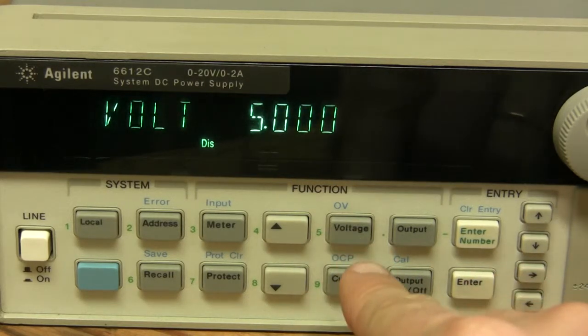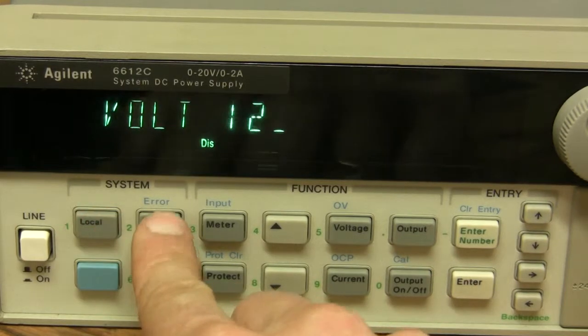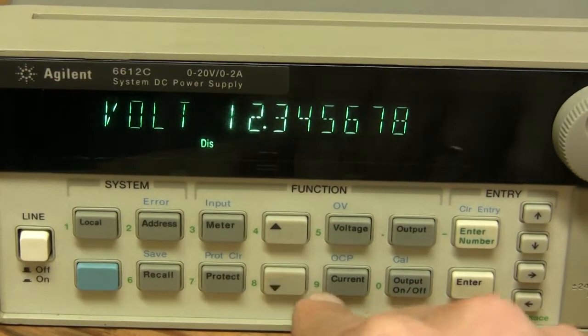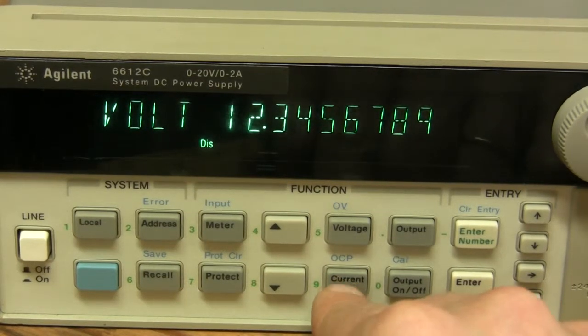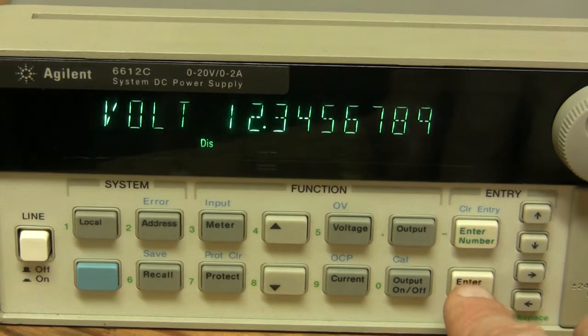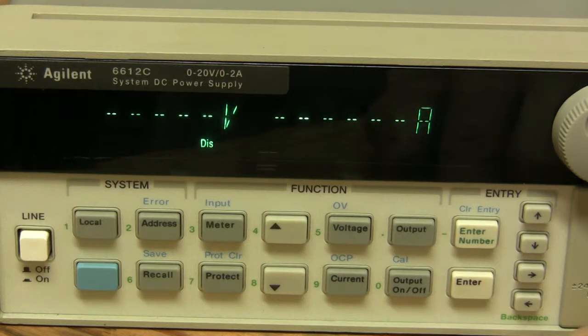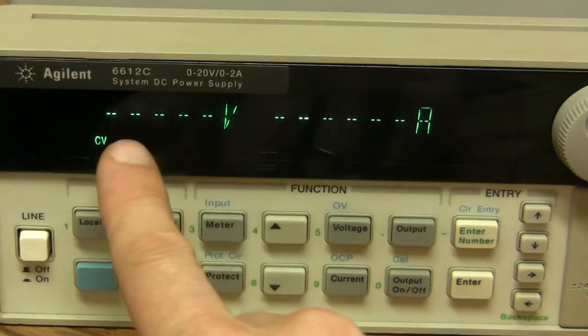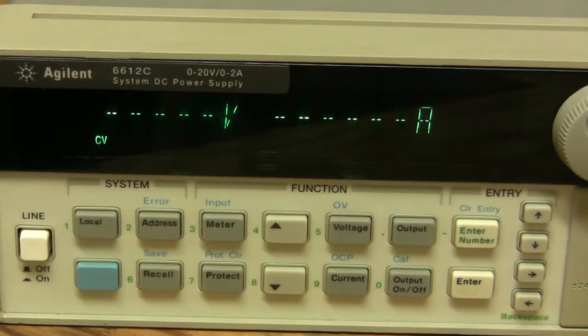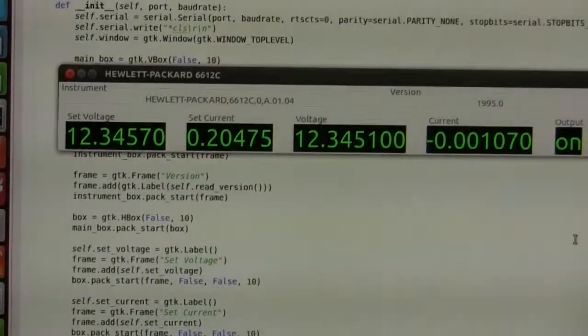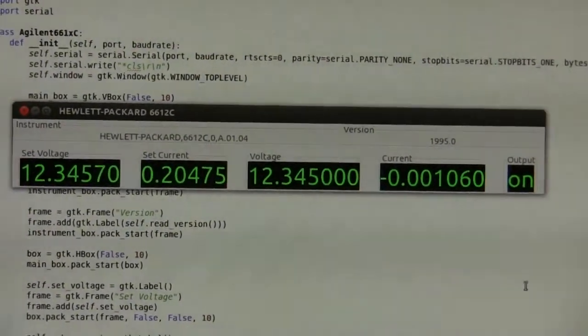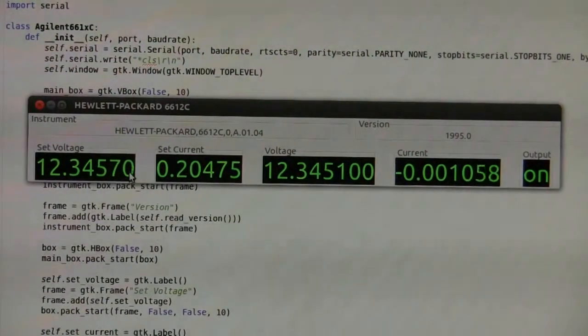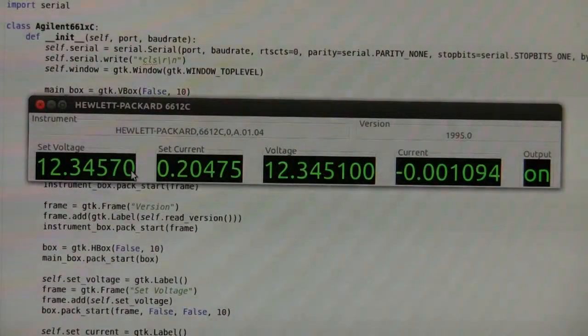Let's try to do this. Let me set voltage to 12.3456789, and that is the limit - we cannot put in any more digits. And then let's see how many of them take effect. So I press enter, let's enable the output. Okay, we can see five digits here in the display. Now let's go back to the computer. What do we see here?